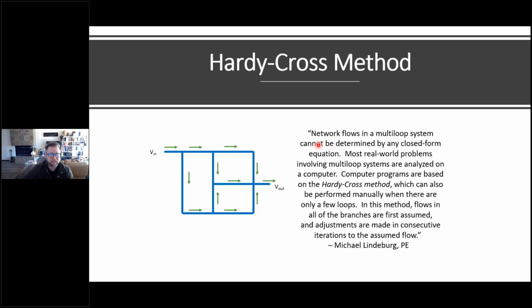And this method basically utilizes a computer program, or you could even use Excel if you're going to do it a little bit manually. And in this method, flows in all of the branches are first assumed, and then adjustments are made in consecutive iterations to the assumed flow rate. So you have to go through and do multiple iterations for a hot water recirculation system, specifically the return, to figure out what the answer is and try to get your system honed in where you want it. And this was what I took a whole semester on. And it seems that ABET may have removed this as a requirement.